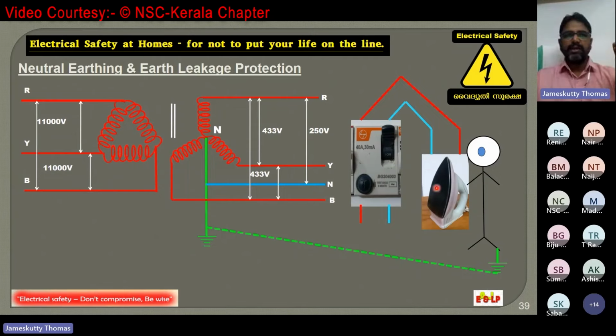Here please note that the fault current passing through the person is returning to the source. See here, it is returning to the source or the transformer through earth to the earth neutral. So for proper functioning of the RCCB, effective neutral earthing is a must.